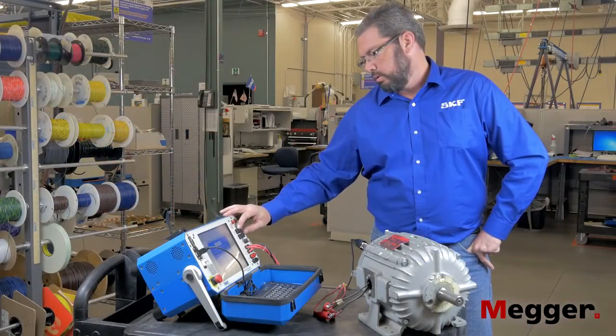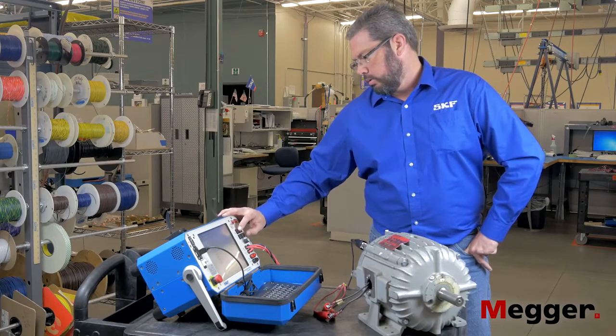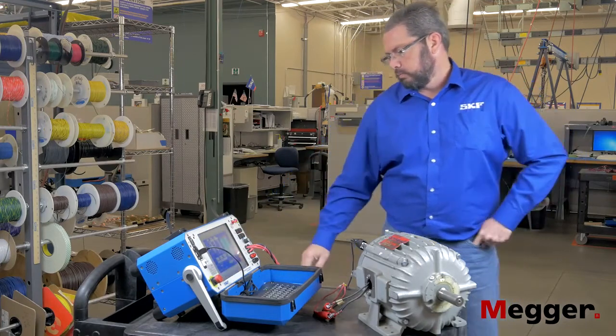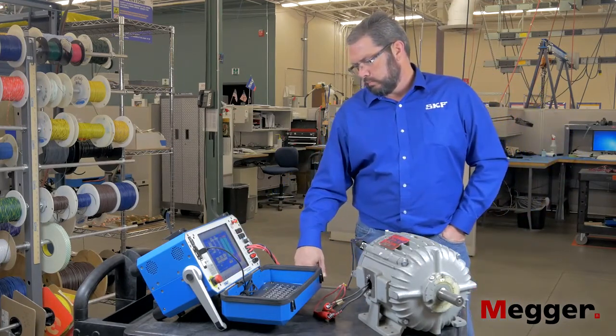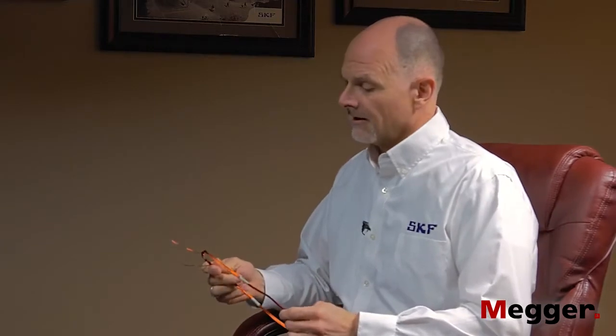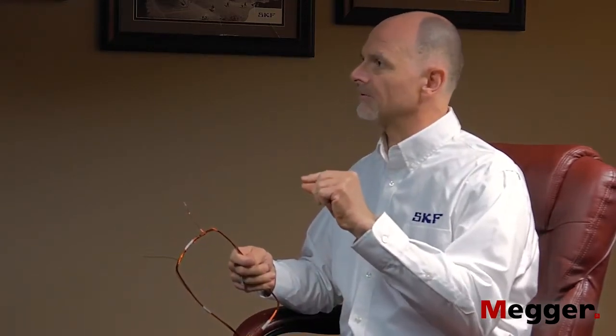Good question. So where does high voltage come from? I mean, you think on a 480 volt motor, a lot of the standards will recommend somewhere around like 2,000 volts. Wow. Well, so like on a 480 volt motor, you've got your basic insulation, copper to copper, and you have your insulation to ground. So you have an inductive circuit. And when you start a motor, you got your contactors that open and close. So you establish a circuit, and then you instantaneously break it before making contact again. So it's when you break that inductive circuit is when you get your high voltage spike.